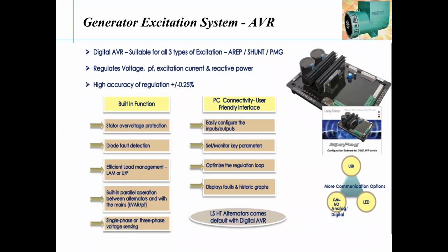In terms of built-in functions, it has protection of stator voltage. It can do diode fault detection, efficient load management, the under frequency roll off or load management system, and built-in parallel operation between the generators or the grid. Both can be done with power factor or KVAR sharing, single phase or three phase sensing, which a customer demands. Fundamentally in India, earlier it was predominantly two-phase sensing. We put one more module to monitor three-phase, but again, it brings a three-phase sensing circuit, easily configurable, customer-friendly. Anybody can do this, play with it like how you are playing with a mobile.